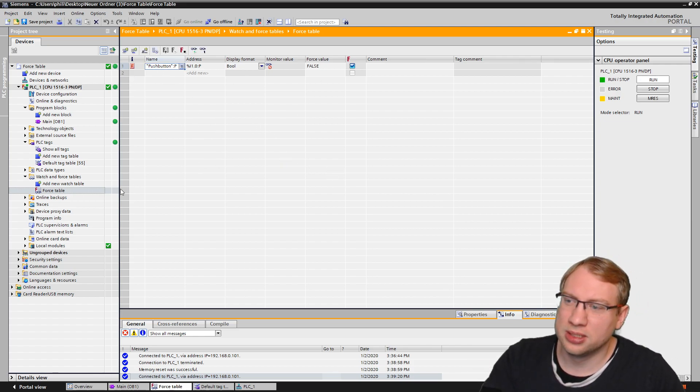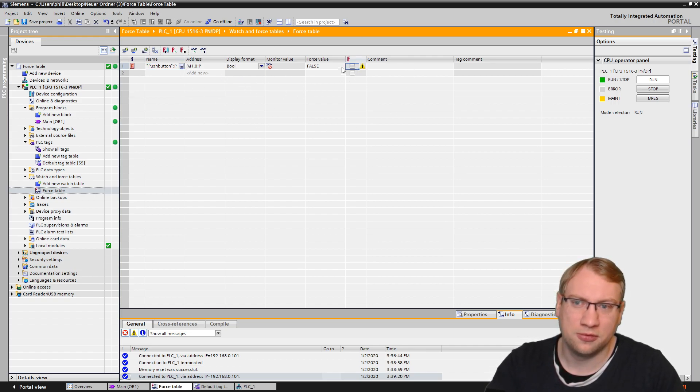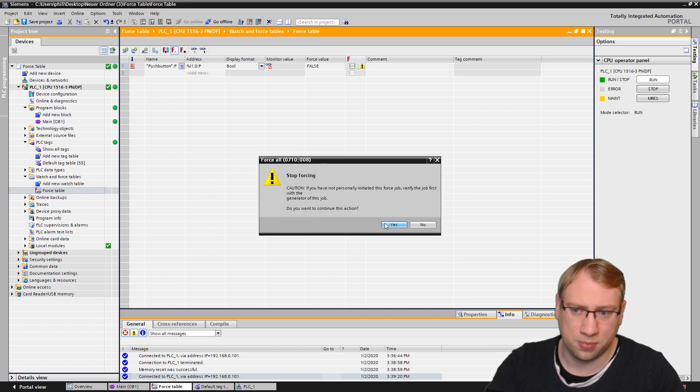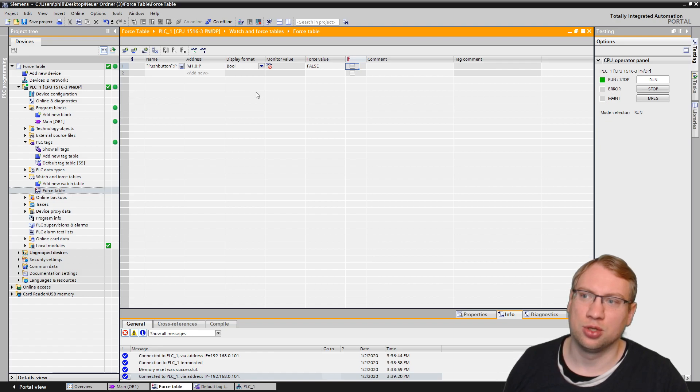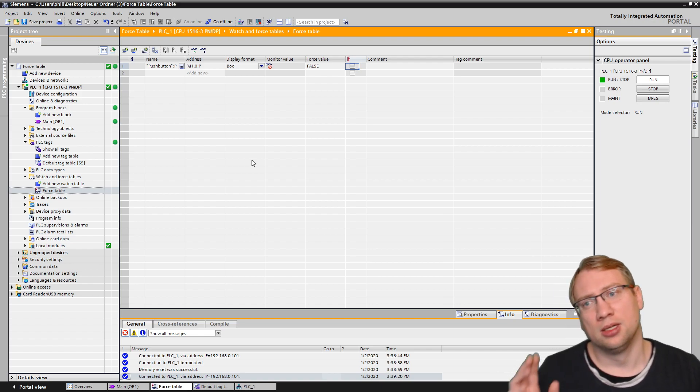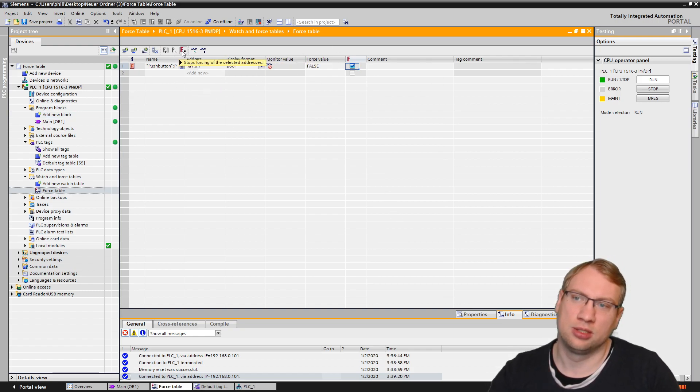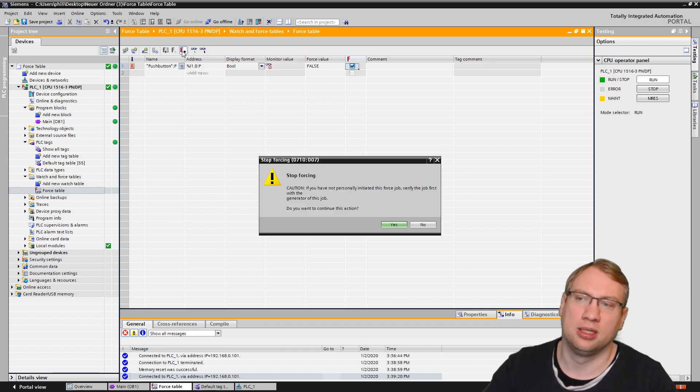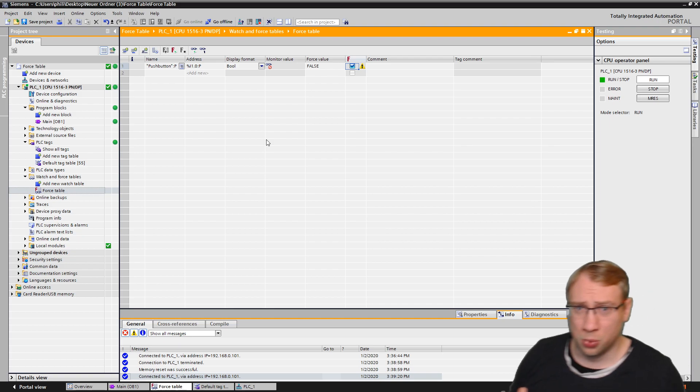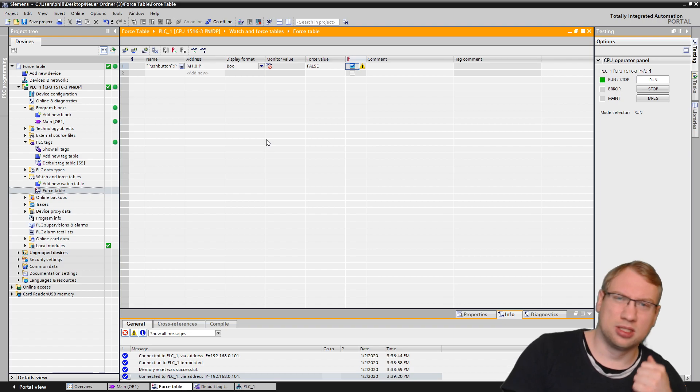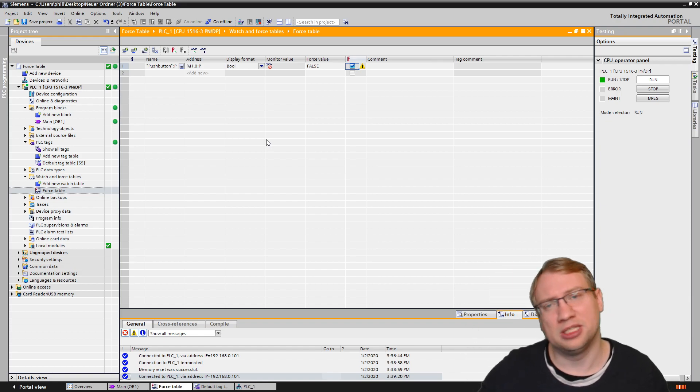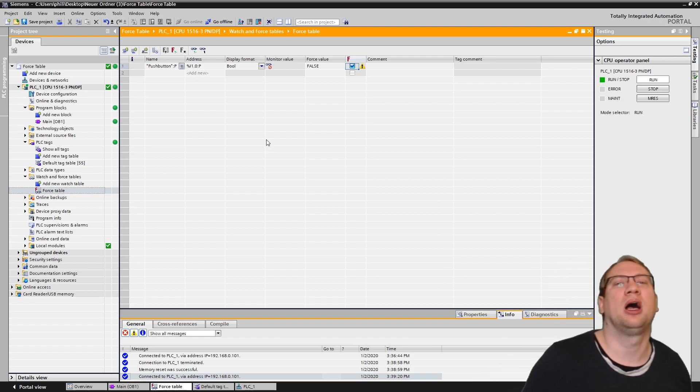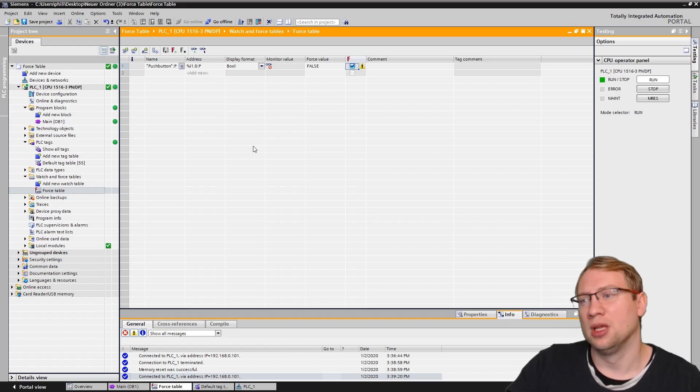What we could do is we go online. We see if force is active. We go in here and we can deactivate the force for every variable that we have. So I deactivate the force here and I say play button and stop forcing. Do you want to continue this action? Yes. Forcing is deactivated. You see maintenance LED is off. The force icon is gone. The force icon here is also gone. So that's one way of doing it. Let's activate the forcing here again. That's one way of doing it. The other way is pressing on top here stops forcing of the selected addresses, which will basically stop the whole force. So those are the ways. You are working with the force table. If you're using the force table, work with the force table. This is the reason why I don't like it too much, because if you activate the force and then something happens to your PC, you're basically screwed. That's how it is. You're basically screwed. That's why I don't really like that. But we'll get there when we are talking about the differences between force tables and watch tables.